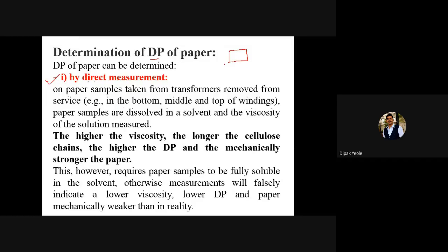For example, where are we removing this paper? In the bottom, middle and top of the windings. We have to take three sets: bottom side winding, middle side winding and top side winding. On that winding, you know the insulation paper is available, which we have to remove for making the analysis.